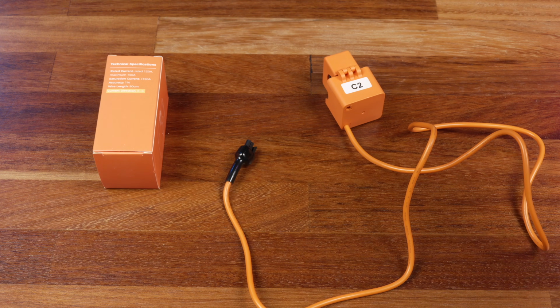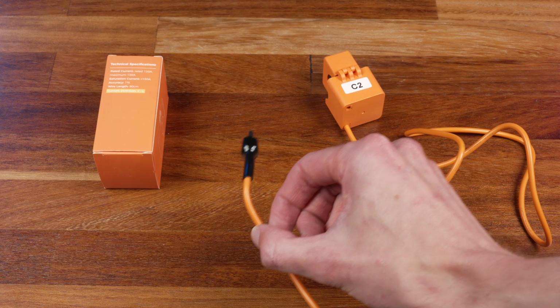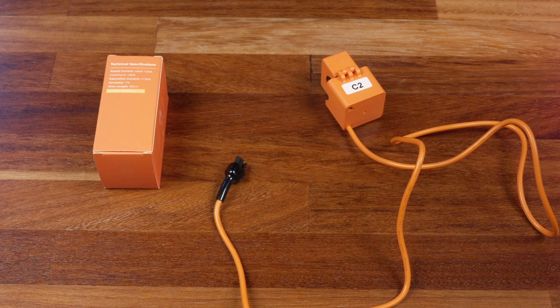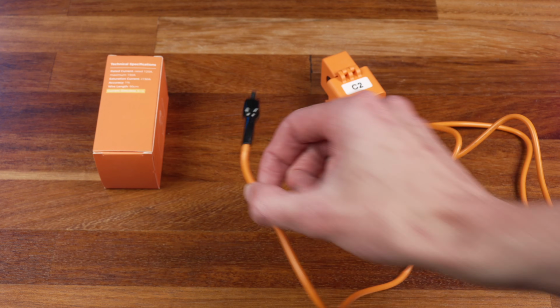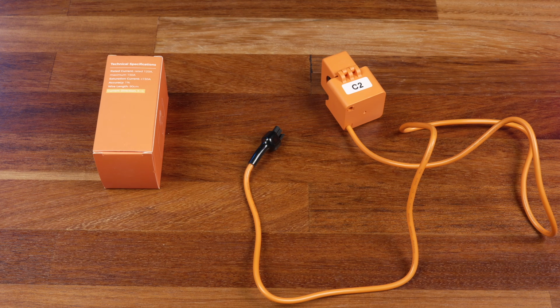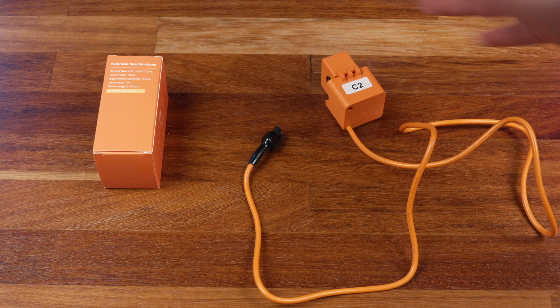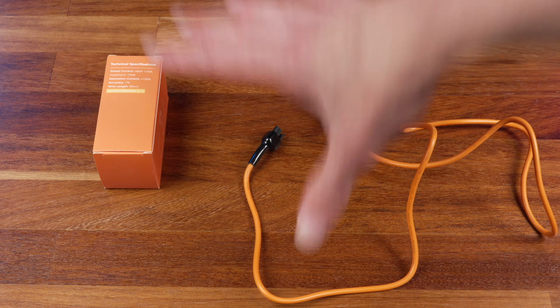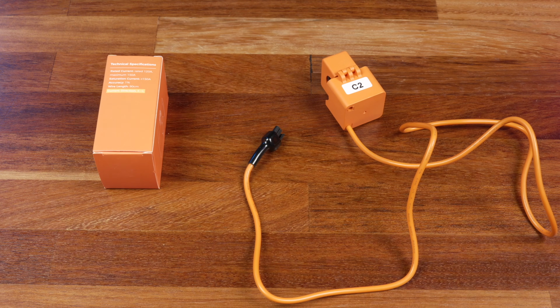Now, the important thing to bear in mind with unburdened current output CTs, which is what I suspect these to be, is that you should not connect these to a wire with current passing through it unless you've either connected this end to the energy monitor or you've at least shorted the outputs of the CT together. If you pass current through these with them just sitting disconnected, you can end up generating a very high voltage on the output connector, which is not only unsafe, but you also risk damaging the CT. So the solution to this is very simple: connect the CTs to the circuit you want to monitor with the power off, then plug them into the energy monitor, and only then turn the power back on. Just something to bear in mind.